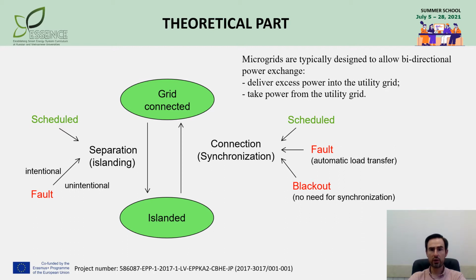If the operating conditions are not permissible after fault clearing, connection with the main grid is required to save critical loads. If it's too late and a microgrid blackout occurred, connection with the main grid is established without synchronization, since microgrid generation is off. However, recovered distributed energy resources shall be synchronized individually later.